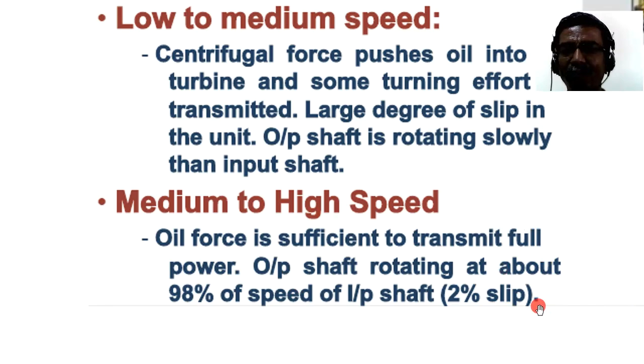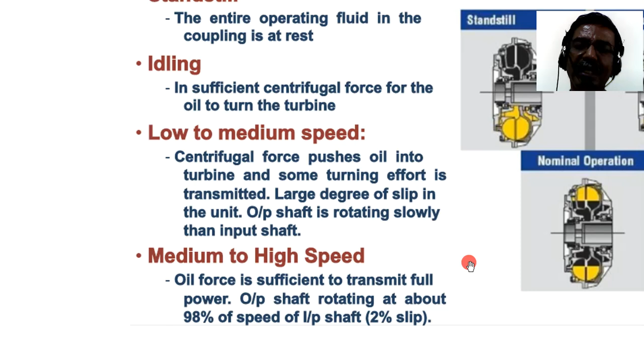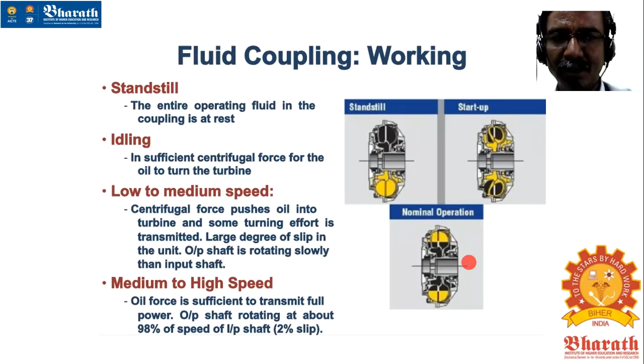But here slip is more, but there is no frictional action. Even if there is a frictional action, heat cannot be produced because the power is being fed because of the kinetic energy and the vortex flow of the fluid inside the fluid coupling. So even though 2% slip occurs, yes, we lose power, but heat is not generated. So that is one disadvantage and one advantage. One disadvantage is yes, 2% slip, but one advantage, even though slip occurs, no friction, no heat generated. So still, the entire setup is running so smoothly and so coolly.